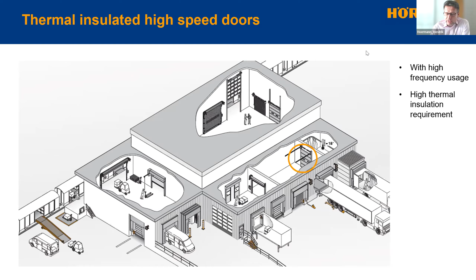But even if you have the best door, you tend to get problems in the tropics when the design is flawed. The potential issues in tropical countries like the Philippines: you get freezing on the door, so it doesn't open properly. You get higher maintenance because the ice impairs proper working of the door, and you even sometimes get ice throughout the entire cold storage area. So this is an energy risk, a safety hazard, and a maintenance cost.